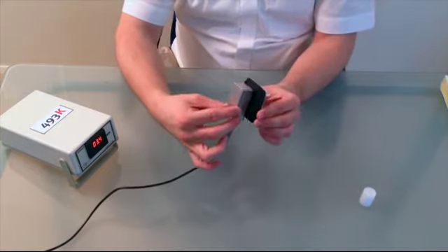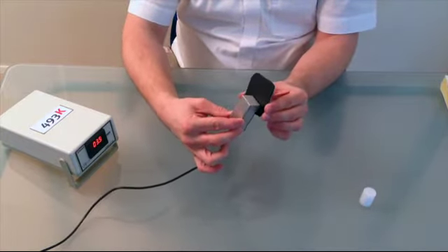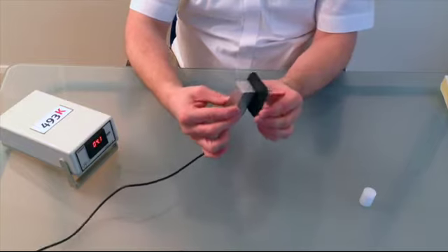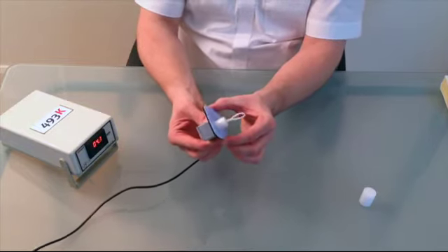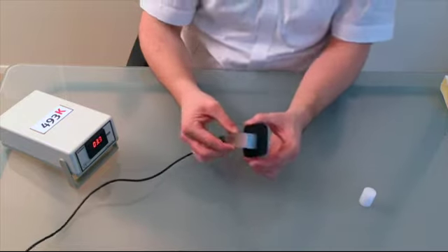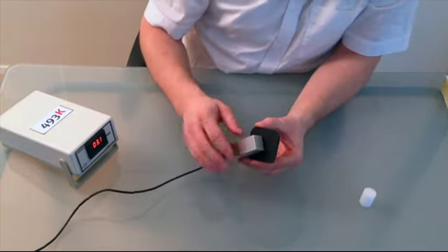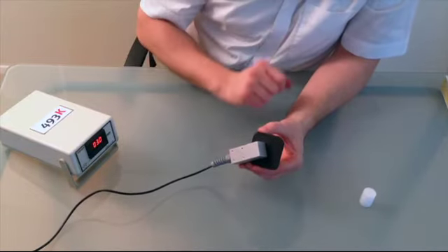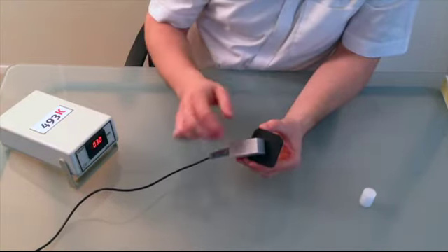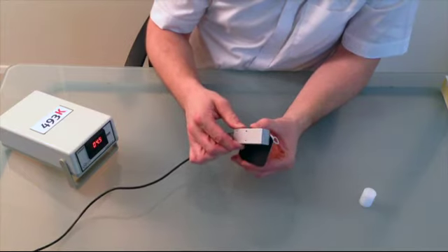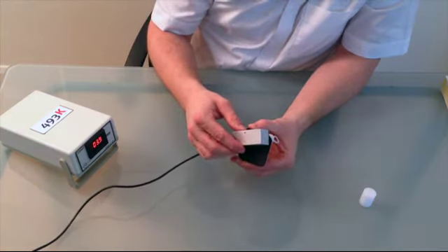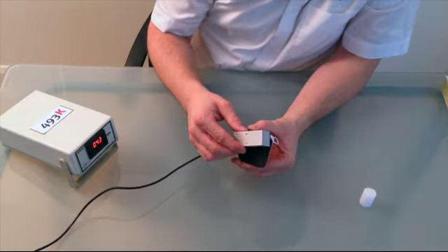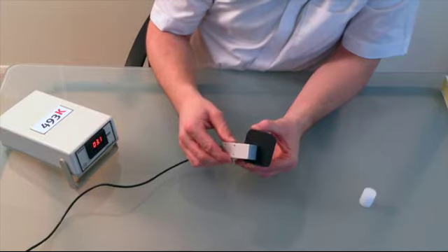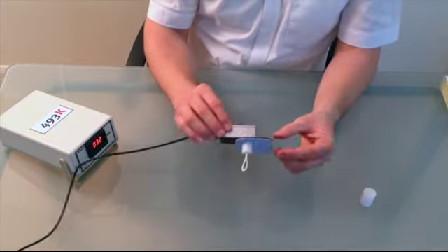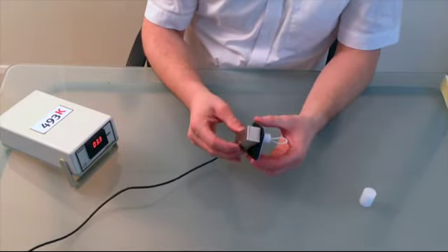The sensing head can then be traversed over the top of the outside of the tank, and you see that the magnetic bullet on the inside will follow and be tracked by it. The readout is given on the digital K-Metron display. And we can see that the thickness of this part ranges from 3.8, or here we have an area of 4.2 down to 3.1. So a considerable variation over a relatively small area.